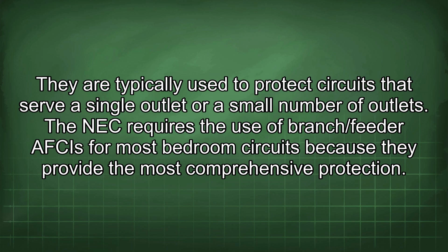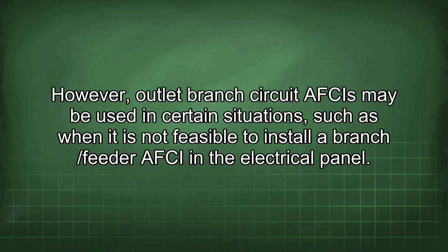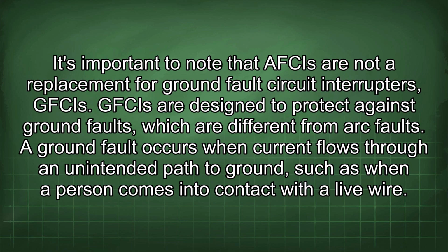The NEC requires the use of branch/feeder AFCIs for most bedroom circuits because they provide the most comprehensive protection. However, outlet branch circuit AFCIs may be used in certain situations, such as when it is not feasible to install a branch/feeder AFCI in the electrical panel. It's important to note that AFCIs are not a replacement for ground fault circuit interrupters (GFCIs). GFCIs are designed to protect against ground faults, which are different from arc faults. A ground fault occurs when current flows through an unintended path to ground, such as when a person comes into contact with a live wire.